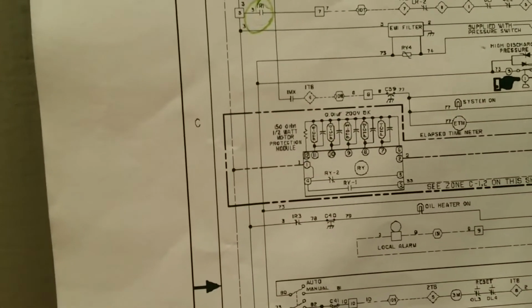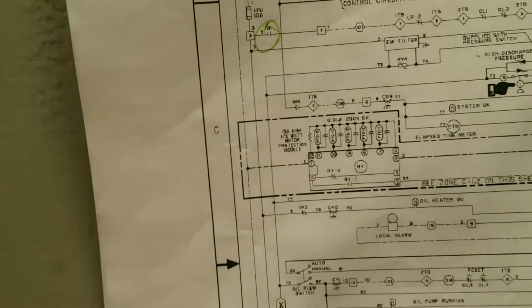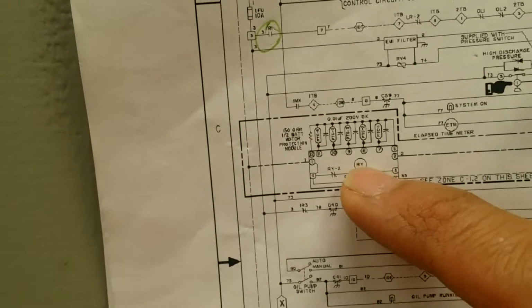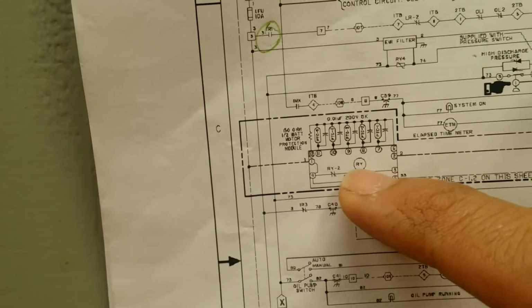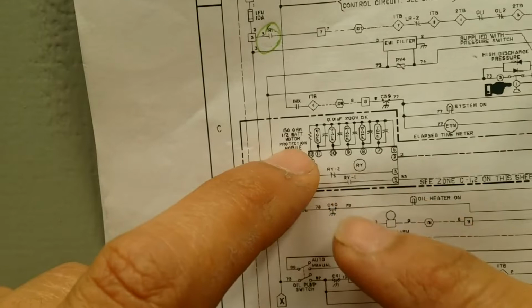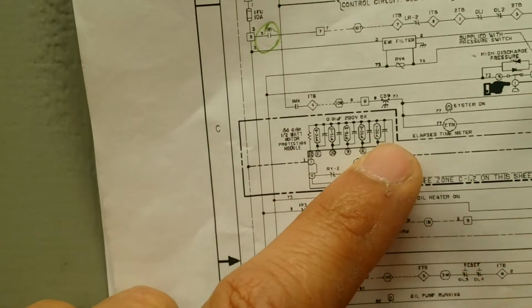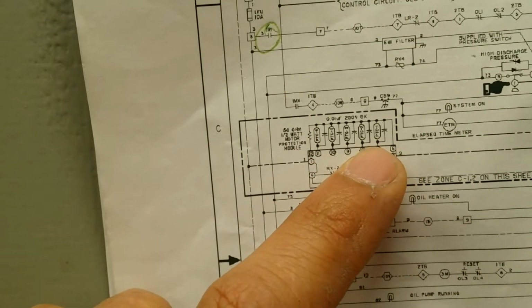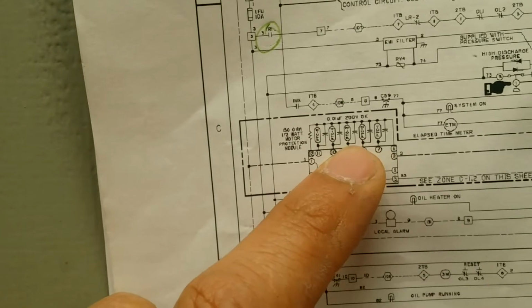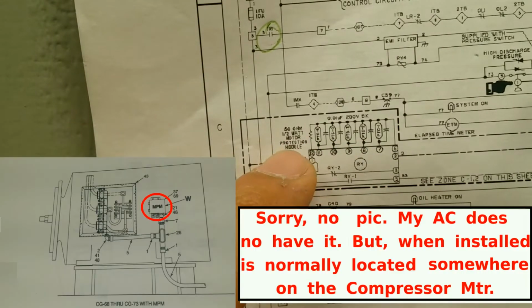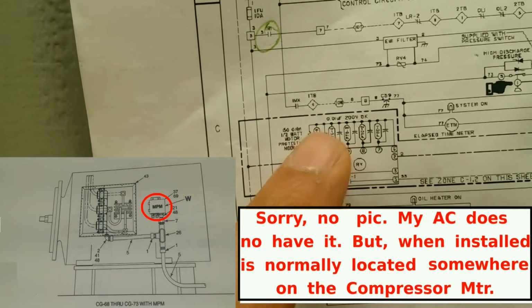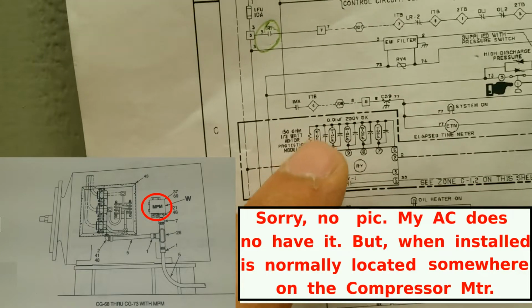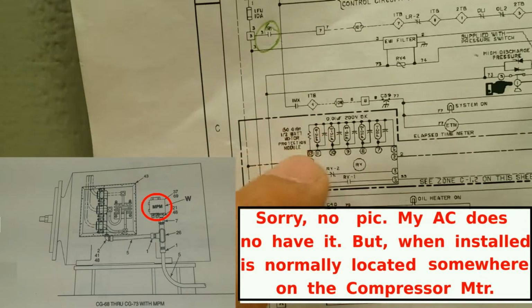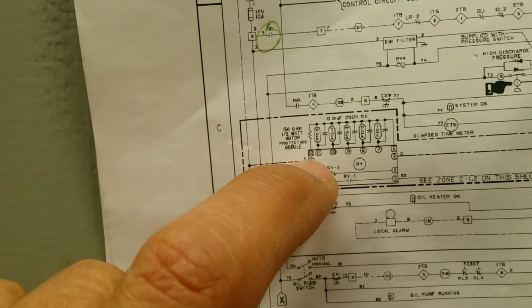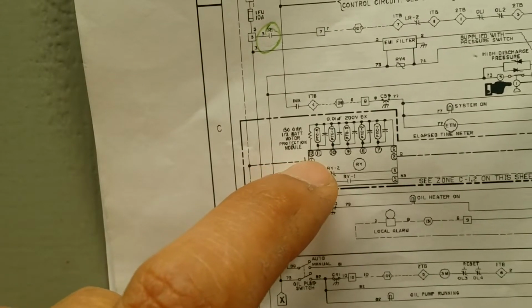Now moving into the motor protection module. There is a relay built inside this module, and it has 5 thermistors. 3 of them are sensing each of the phases of the motor, and 2 are 1 per bearing, at least for my side. All of them have to be good. If one of them burns up, I'm going to have to get a right size resistor and put it to jumper it to simulate that one is good to go.